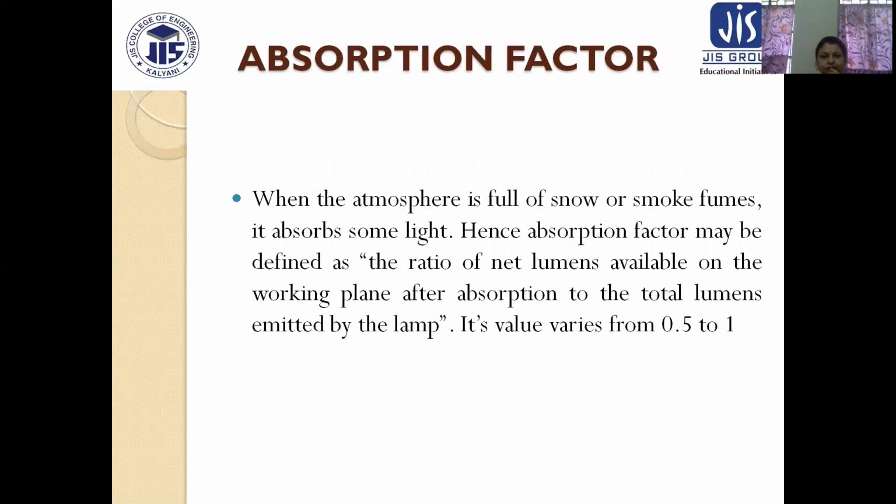Okay. Now, absorption factor. When the atmosphere is full of snow or smoke fumes, it absorbs some light. Hence, absorption factor may be defined as the ratio of net lumens available on the working plane after absorption to the total lumens emitted by the lamp. Its value varies from 0.5 to 1. Okay.